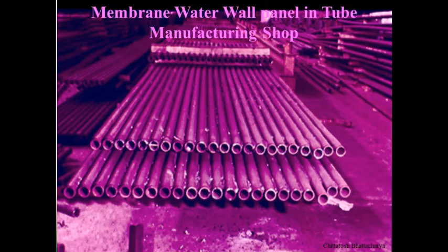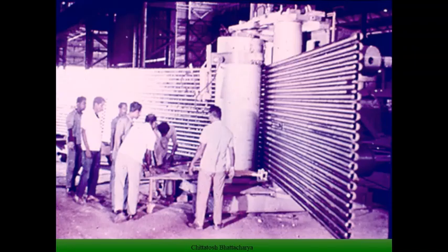But as there is only addition of latent heat of vaporization, the entire water walls are supposed to be at constant temperature, because there is no rise in coolant temperature. So there is a constant temperature difference between water and the tube metal temperature.